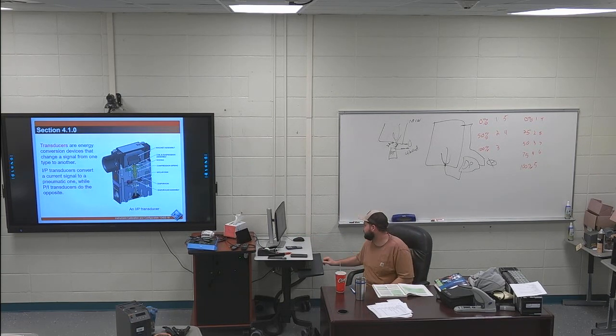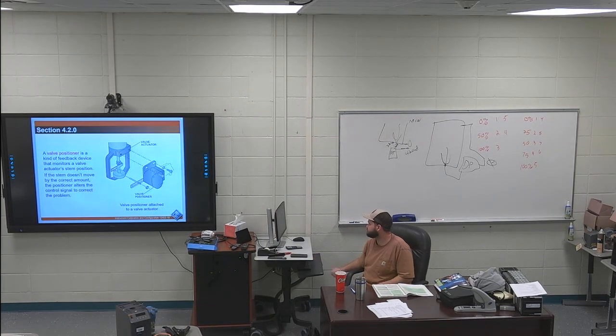Control valve positioners, 420. The whole first paragraph is highlighted, and you're going to have 3 questions come out of this. The function of a control valve positioner is to compare the valve stem's position to the input signal and manipulate the actuator so that the position matches the input signal. The positioner is usually connected to the actuator stem by a mechanical link. That half of a sentence is an online test question.